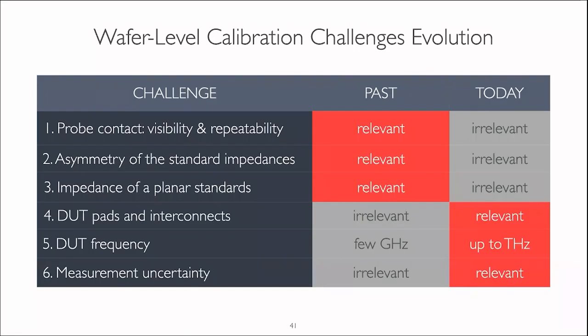For instance, probe contact visibility and repeatability of the measurement data, related to bad visibility of the probes. That was relevant for the first generation of wafer level probes, and for today's generation it becomes significantly less relevant, and for some probes even irrelevant at all. Asymmetry of the measurement standards.